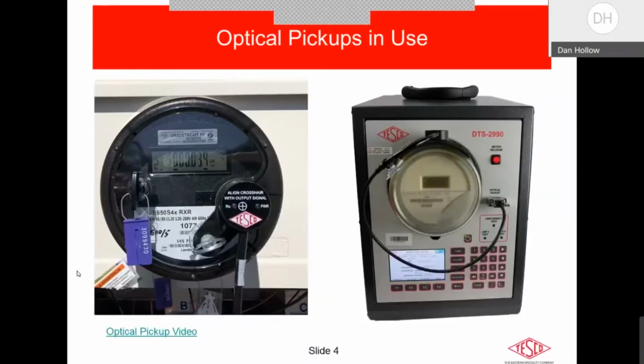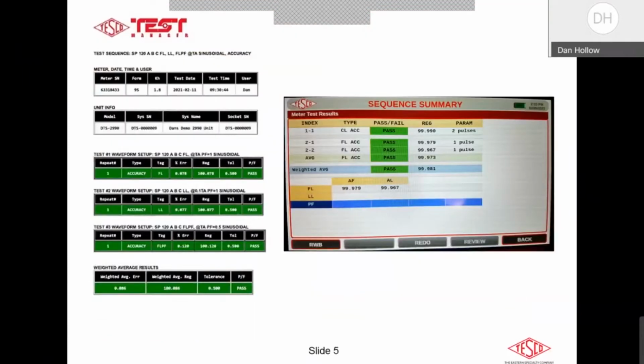All right. So let's move on. These are what some typical reports would look like. The one on the left is a report from a test board, from that test board we just saw. So it will have all the information on the meter, the Kh value, the form factor, when it was tested, who tested it, what it was tested on. And it would also have all the results from a full load, a light load, a full load power factor test, and then ultimately at the bottom, a weighted average, which takes into account all three of those tests and gives them the weighted average.